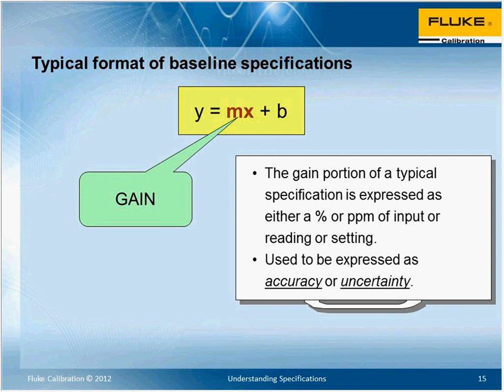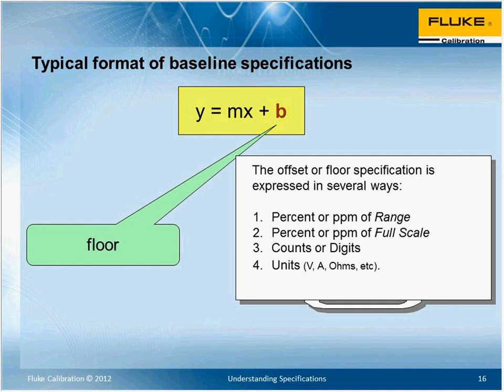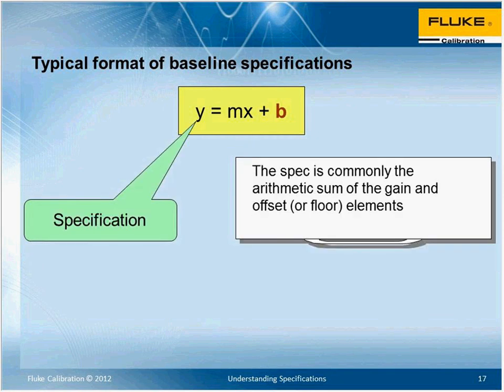If you are new to specifications and understanding them, we have a webinar coming up next, actually part of the Back to Basics seminar. After evaluating these specifications, they're basically formatted the same across calibrators, and the MX portion is your gain portion, usually expressed in either a percent, ppm, or of input. So make sure that as you're evaluating it, you know which one it is. And then you have your floor spec, which is expressed in one of several ways: either a percent or ppm of range, ppm of full scale, counts, digits, or units. So this is basically the adder, which once you put it all together will give you your specification.